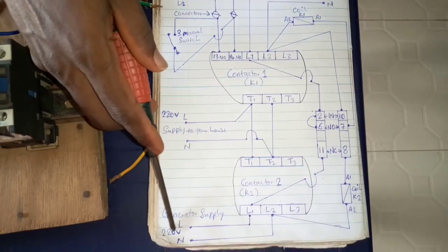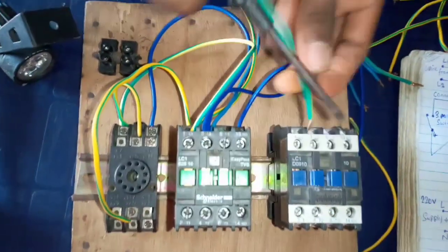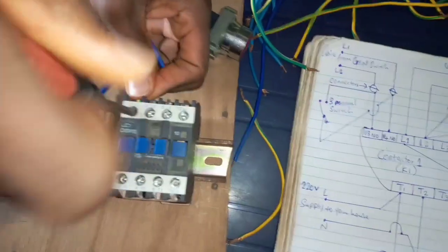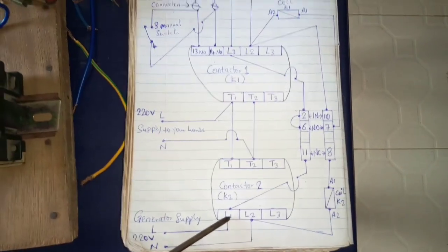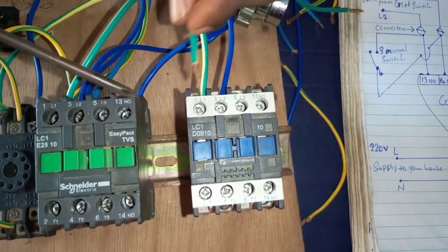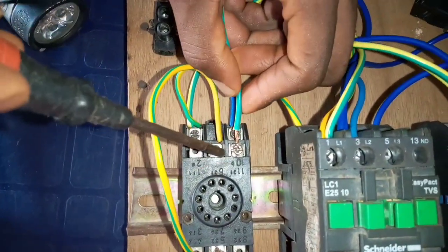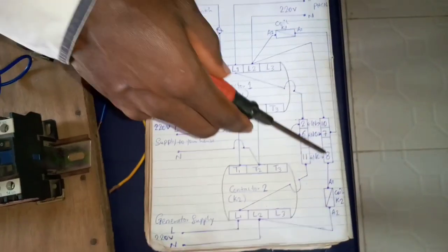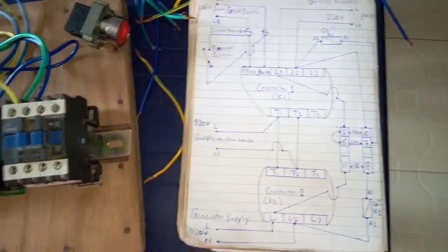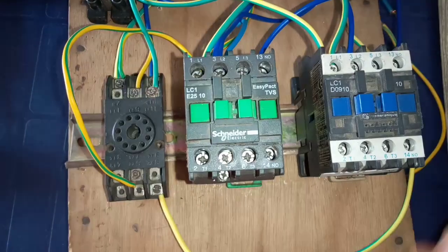Looking at the diagram again, for the generator supply: generator supply goes to L1 and L2 of contactor 2. So we connect generator supply to L1 and L2 of contactor 2. Then L1 of contactor 2 connects to terminal number 11 of the pin relay. Terminal number 8 of the pin relay connects to terminal number A1 of contactor 2 — this is the terminal number A1 of contactor 2.